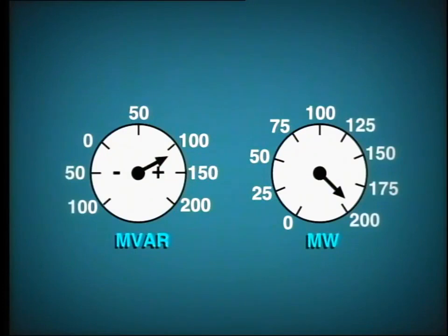The result of this is that we could easily overheat the generator windings if we had a high megawatt output plus a high megavar output. Definite limitations are placed upon the combined total output of megawatts and megavars.